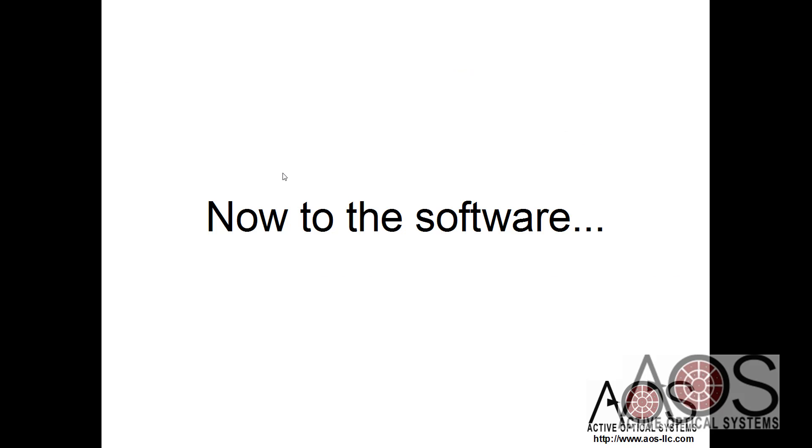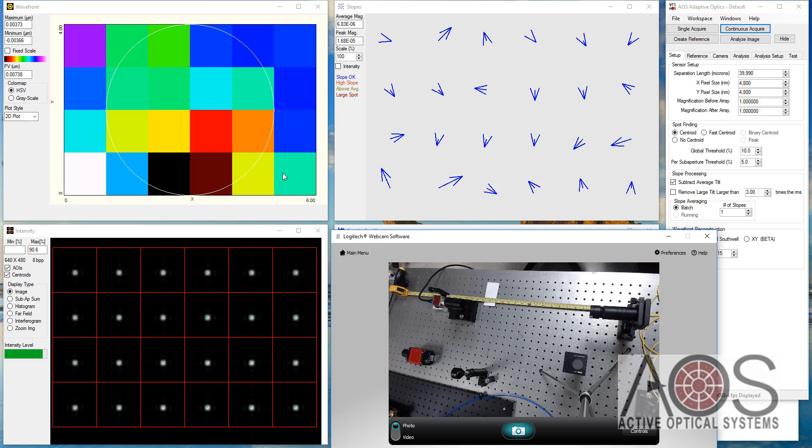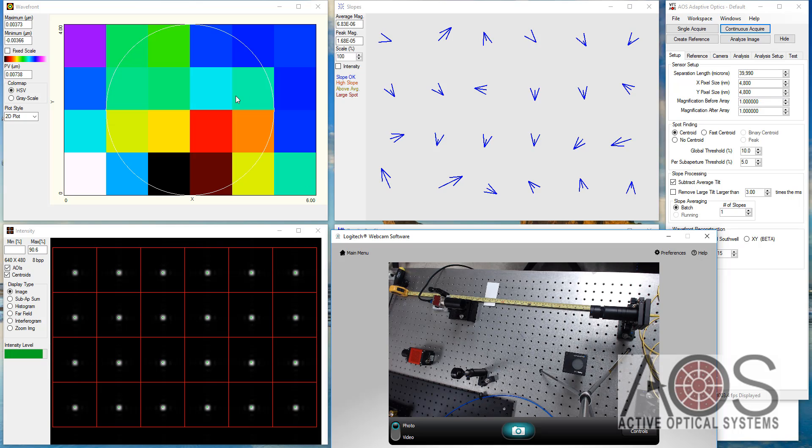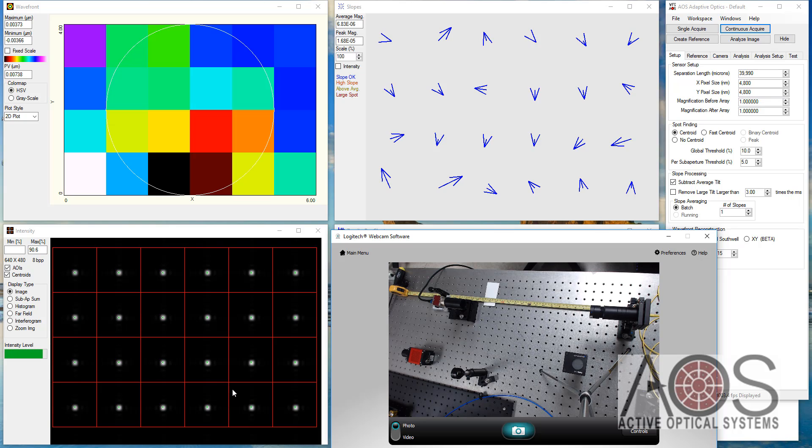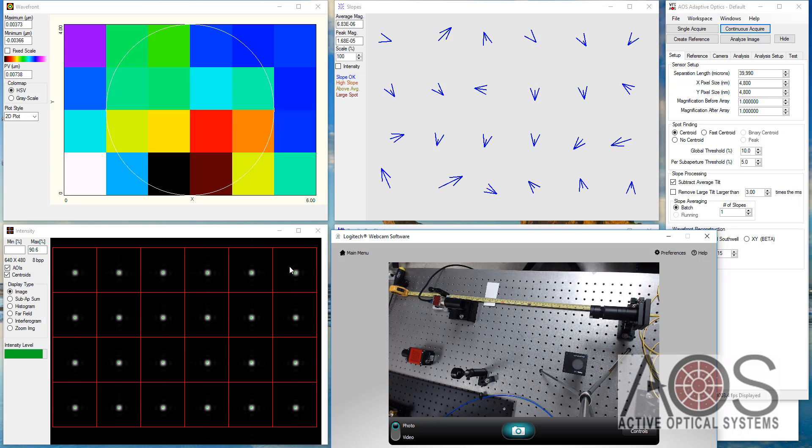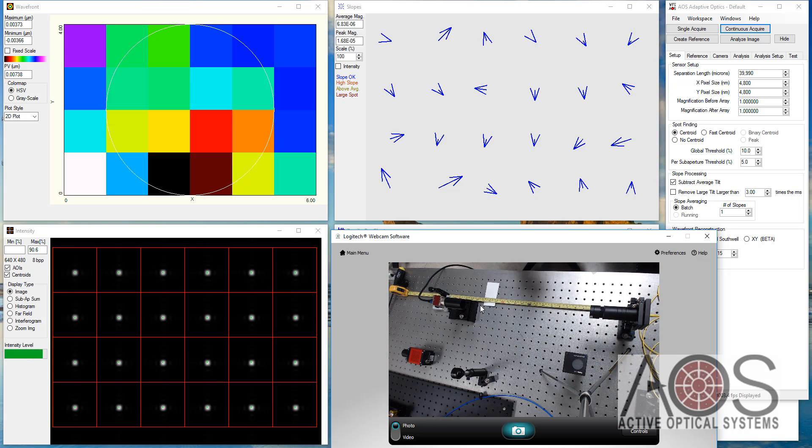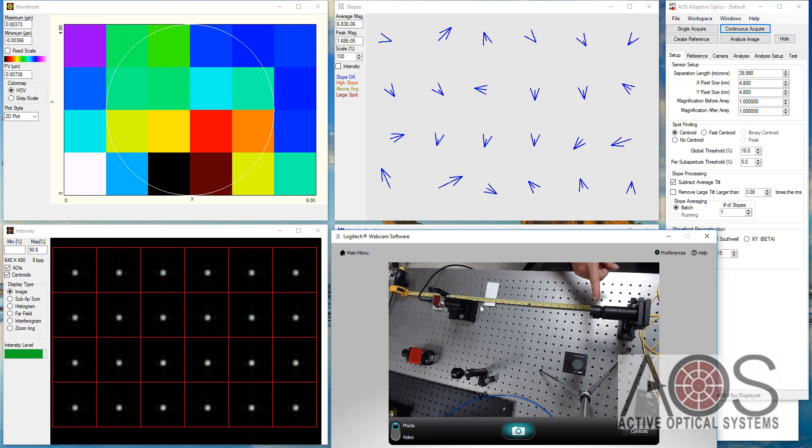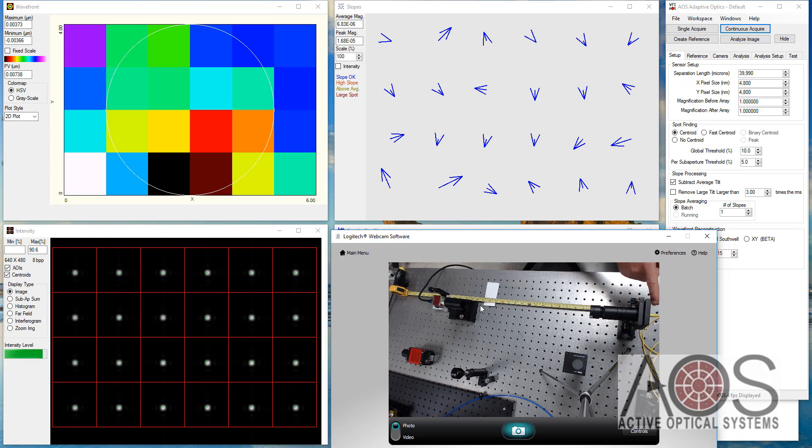Now to the software. Okay, so this is the AOS software loaded up. This is a very low resolution wavefront sensor. It was actually designed to be high sensitivity and very low resolution. This is a live view of the optical setup where we have the wavefront sensor here and this is the collimating lens and the fiber tip back here.